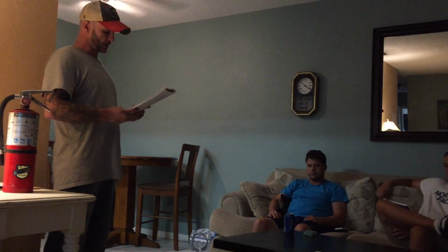In addition, the tremendous surface area of the finely ground particles allows it to absorb large quantities of heat, which lowers the temperature of the fire. Dry chemicals are effective on Class B and Class C fires. Class B fires are the flammable liquids and gases, and Class C are the energized electrical fires.